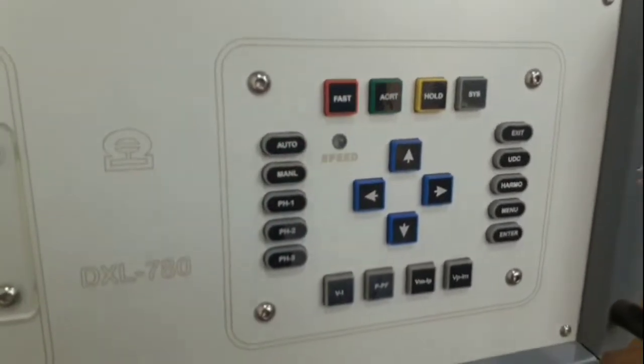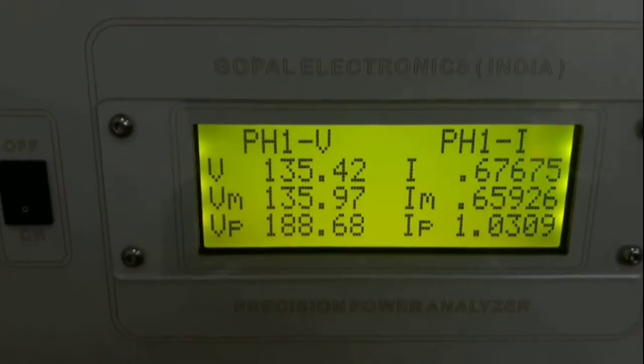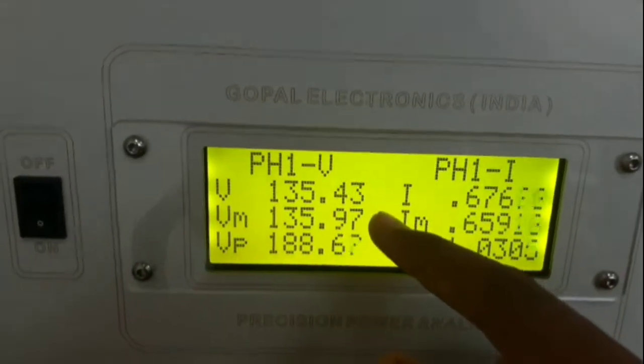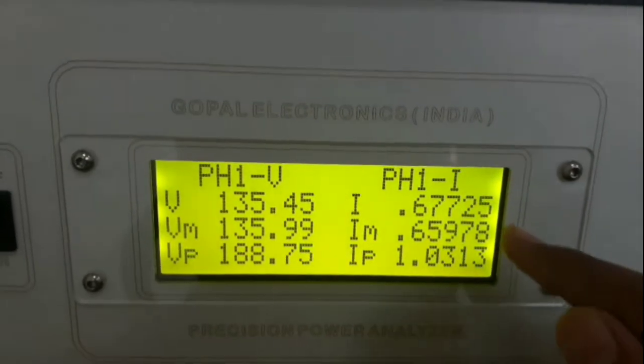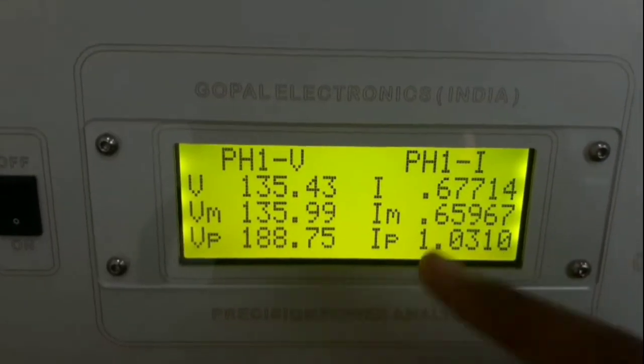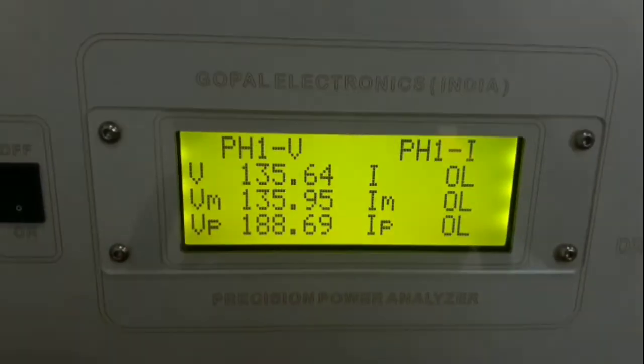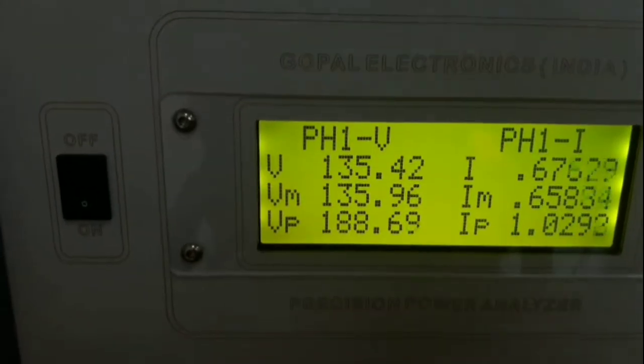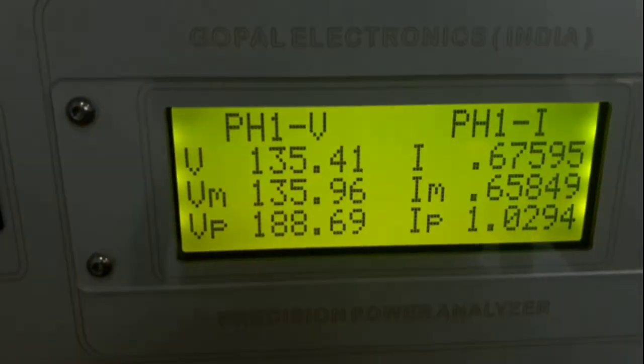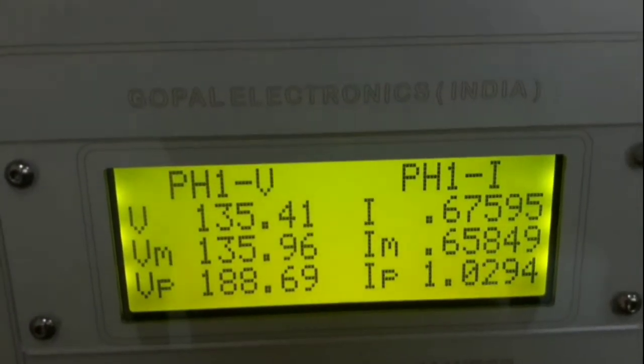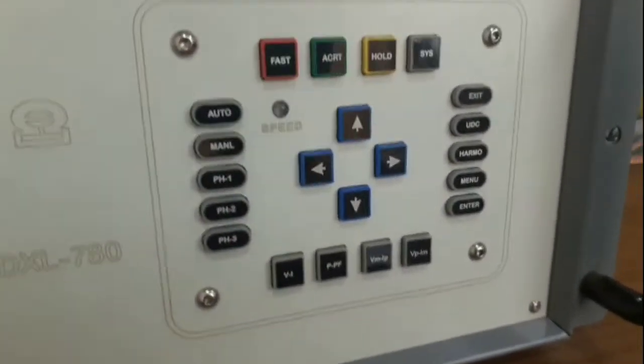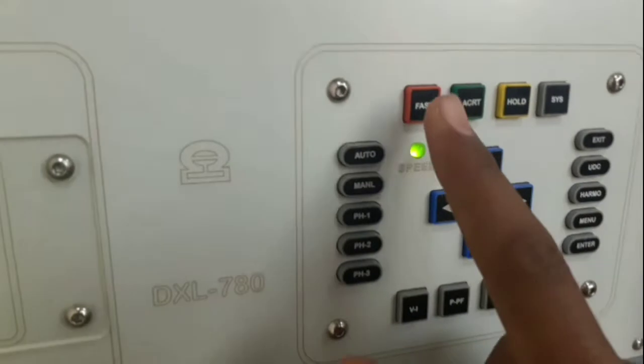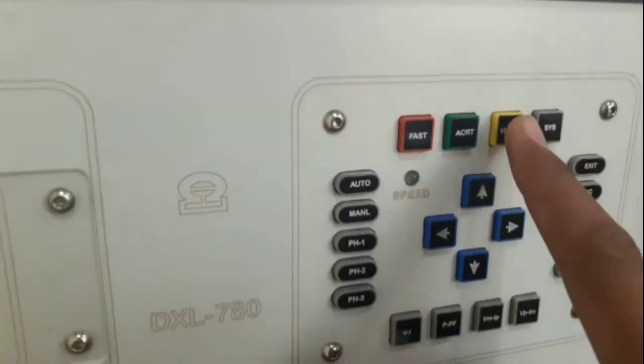If you want to see parameters for phase 1, press the phase 1 key and now it is showing parameters of phase 1: VRMS, V mean, V peak, IRMS, I mean and I peak. This is showing in fast mode, and if you want to see it in accurate mode, press the accurate key. Now it is showing the same data of phase 1 in accurate mode, and if you want to take a reading, press the hold key. By holding data you can take a reading. In the same way you can take readings for phase 2 and phase 3 in both modes, fast and accurate, and by holding them you can get the reading.